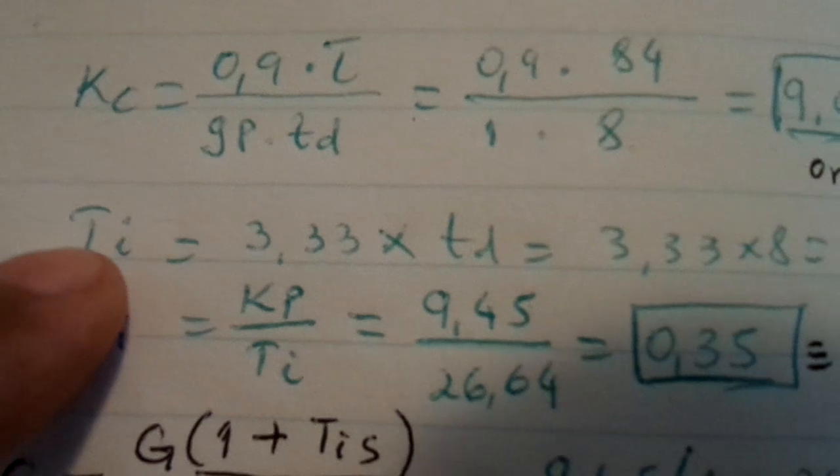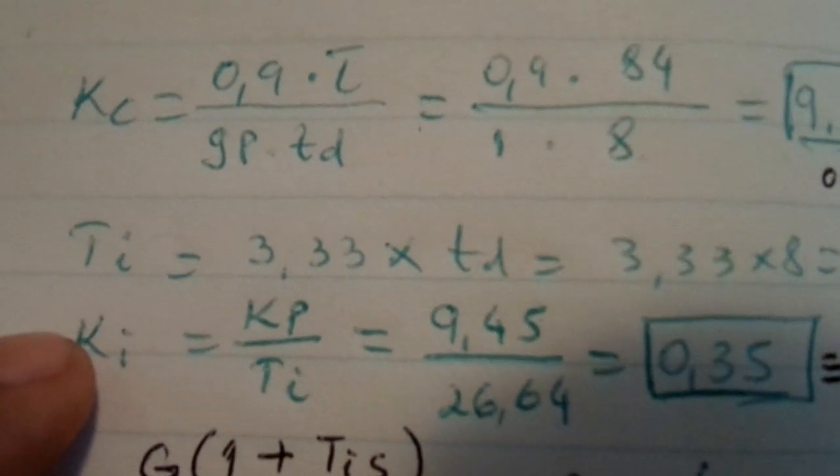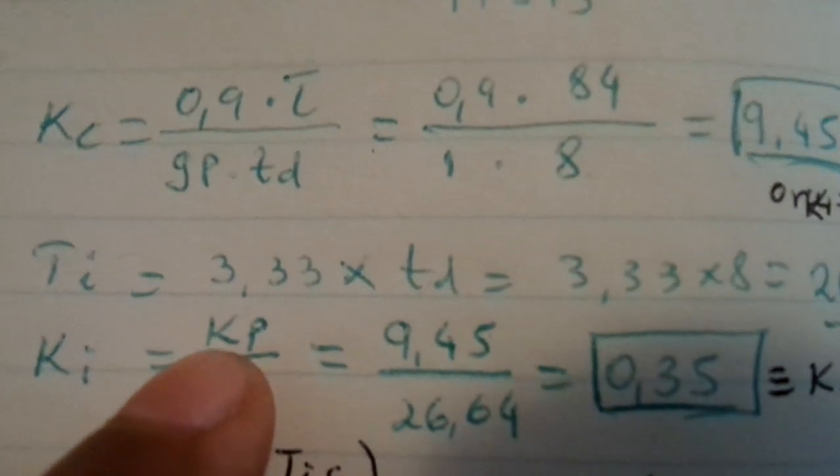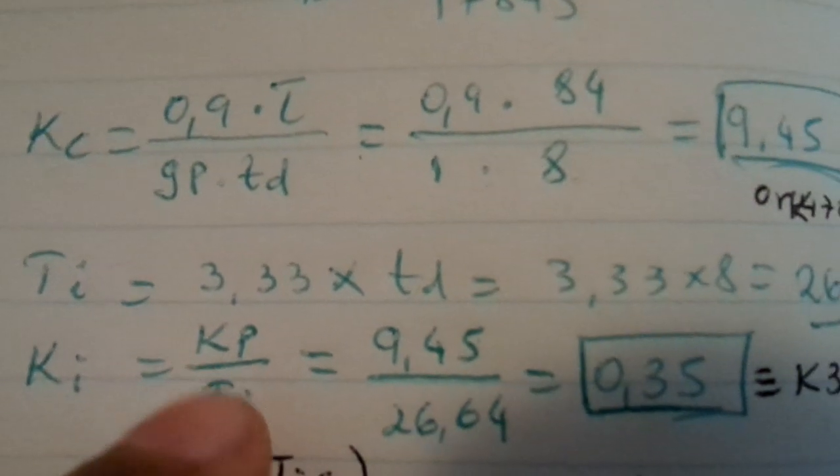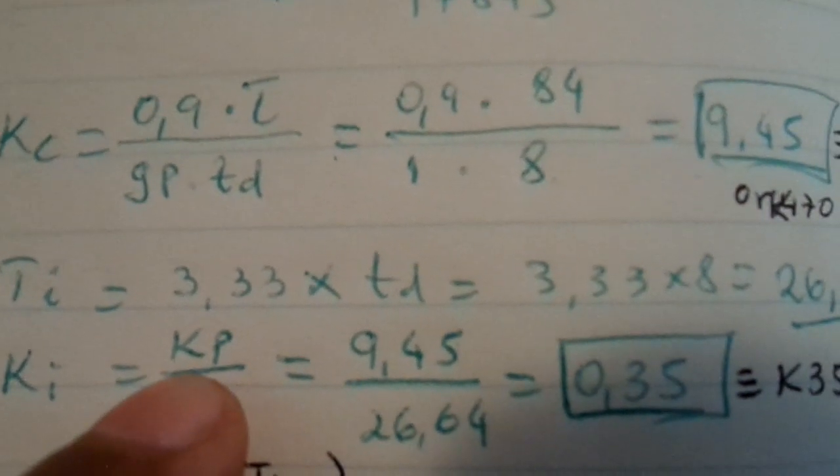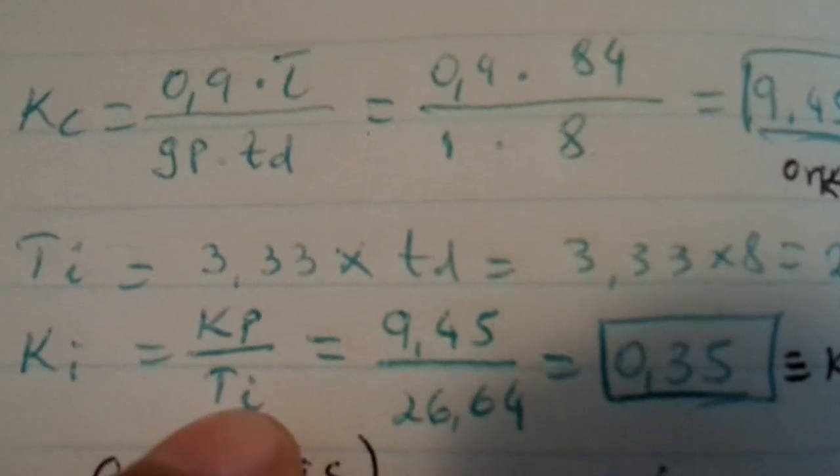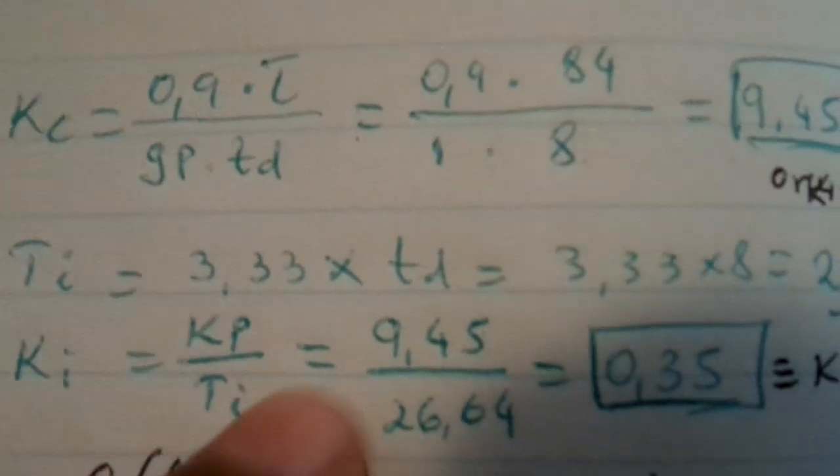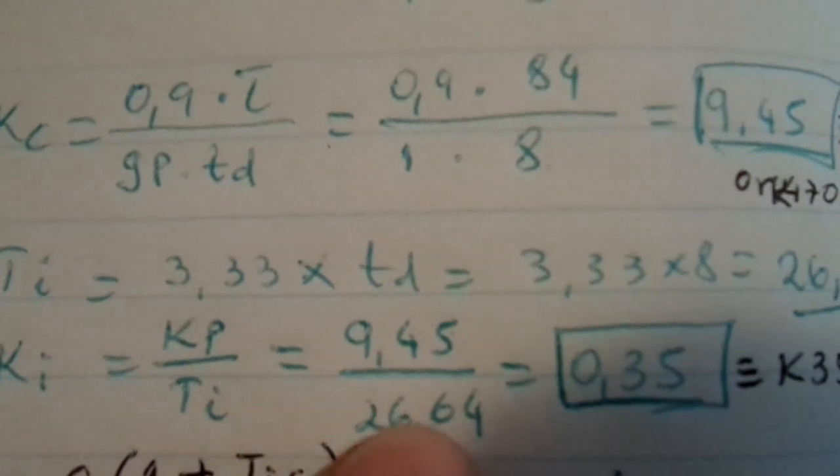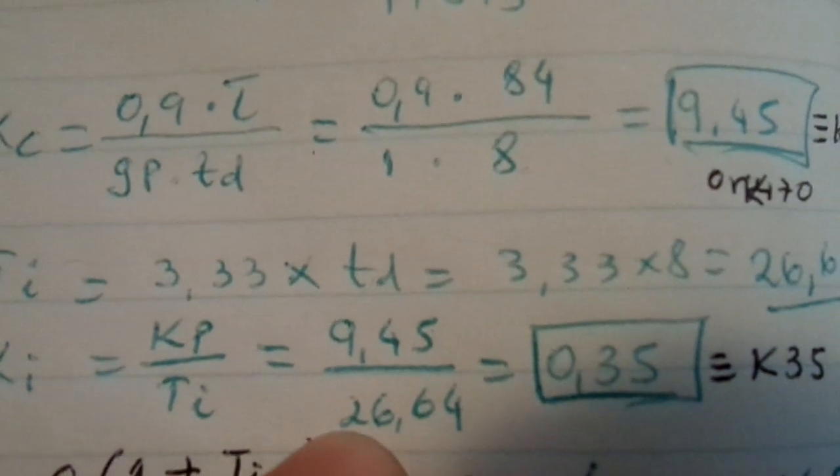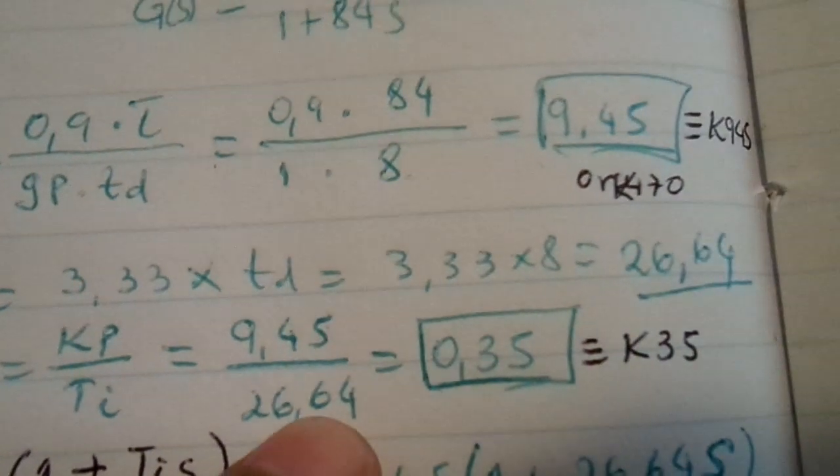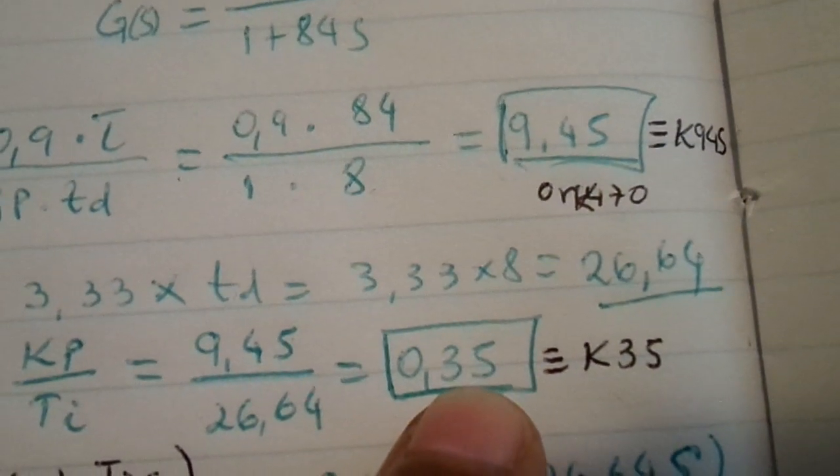So now, that's integral time. For me to find the integral gain, that will be according to the same Ziegler-Nichols: the controller gain over integral time. That's 9.45 over 26.64, and I got 0.35.